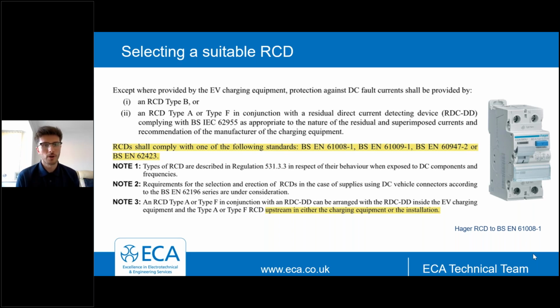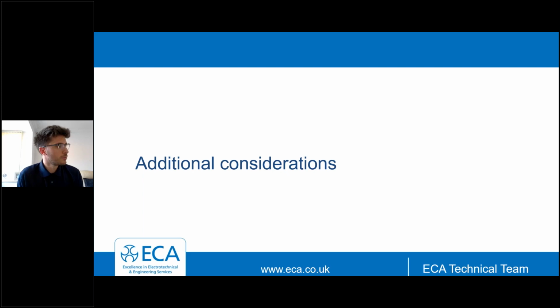So to summarise this bit, RCDs need to be of a suitable type, they need to switch all of the live conductors, and they shall meet required British and European standards. So those are the key bits of focus from section 722. I'm now going to look at some further considerations.